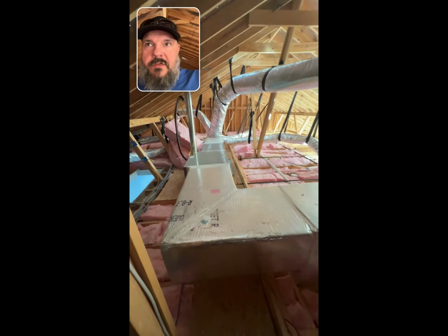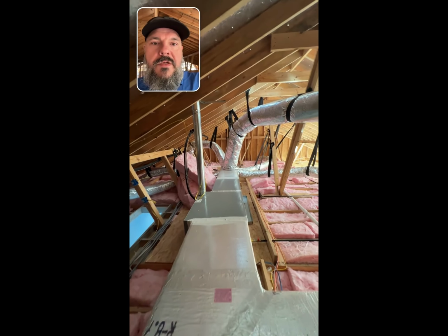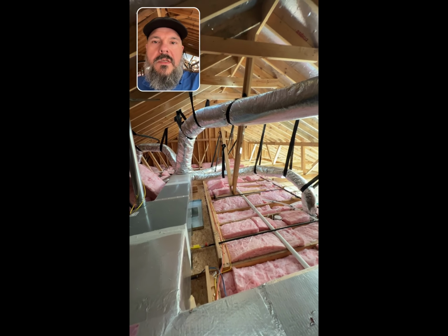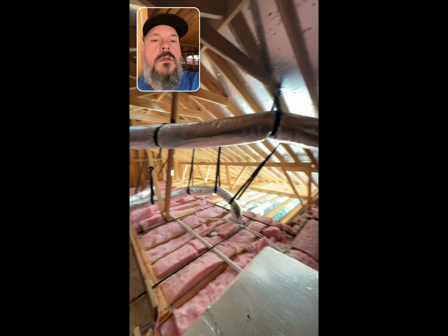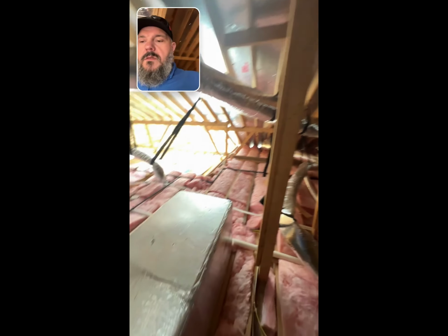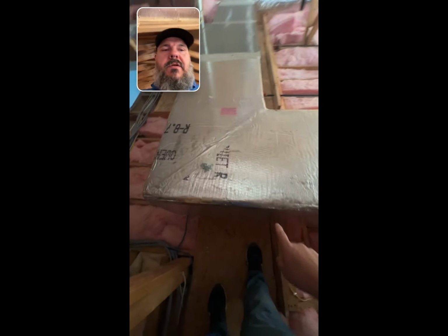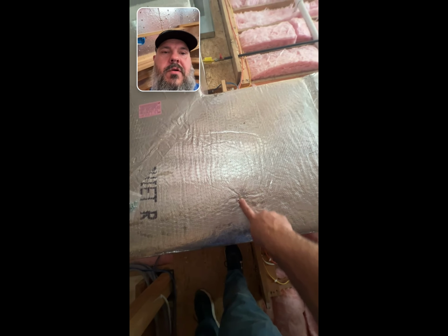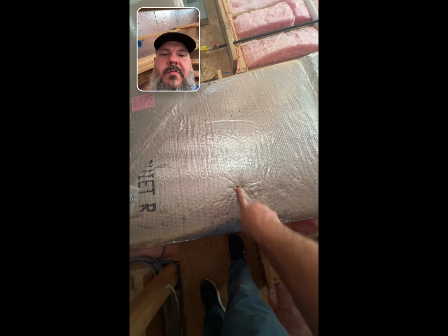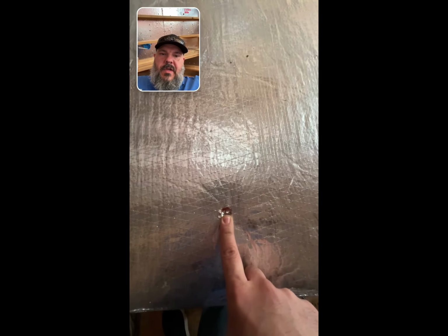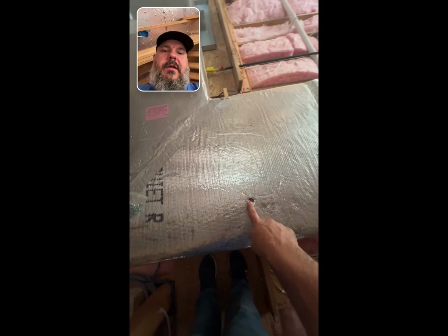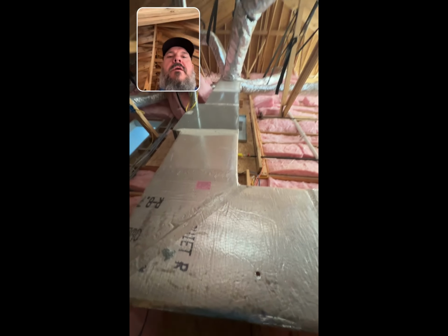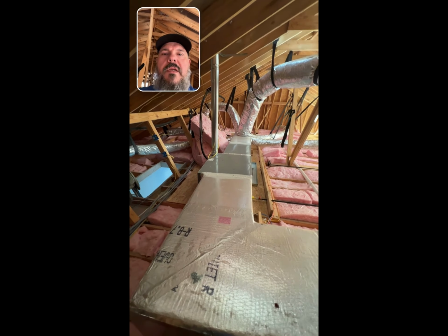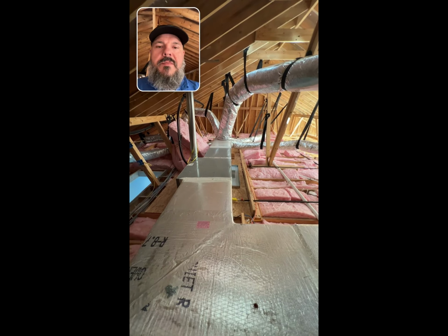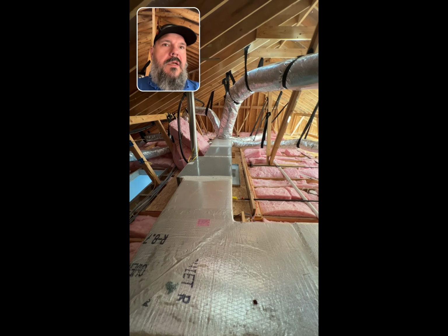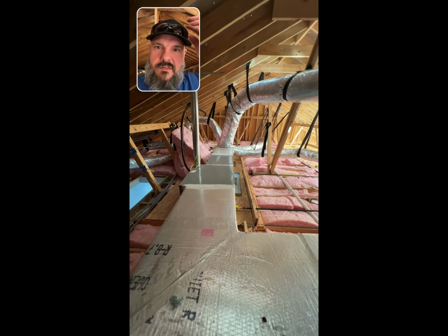So you can see we have all flexible ductwork up here. We have no rigid pipe, no metal. Once again, the cheapest bidder gets the job, and the job reflects it. All of my supply and return air plenums are fiberglass ductboard. This is a very cheap, not durable material. I can literally stick my finger through there. No critical thinking goes into the design aspect of how these units are installed in the house. They just kind of throw them in however they see fit.